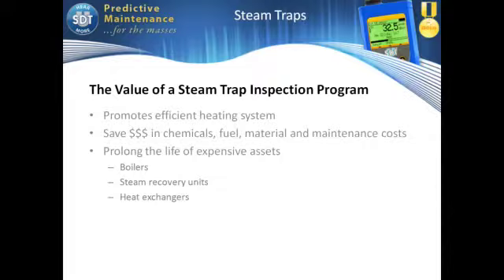So sometimes having an inefficient steam system can be a big, big cost. When you've got leaks, you've got costs associated with extra chemicals needed for treating the water, extra costs of fuel, extra costs of all sorts of materials and labor. Ultrasound can also help you extend the life of the very expensive assets in your steam system, like your boilers and your condensers and the heat exchanging systems and the steam recovery systems and all the rest of it. So testing for tightness, testing for leakage in those areas, is very, very important to be done. And ultrasound is definitely the best tool to be doing that with.